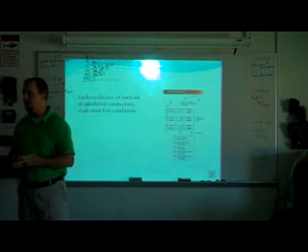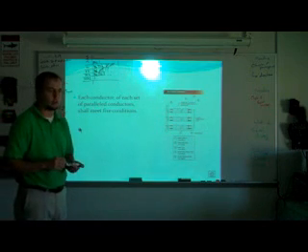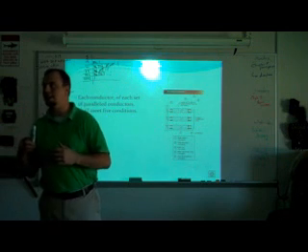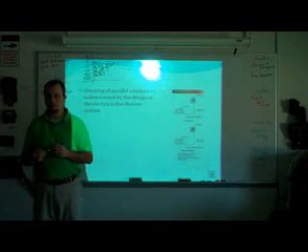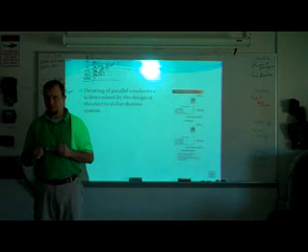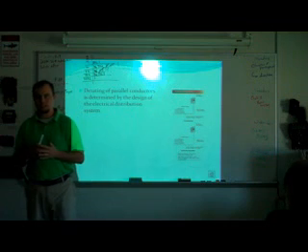Why do they have to be mirror images? Why do you think, Pat? Not so much voltage. One doesn't get more current. Okay, you want them to be exactly the same so that they share the current exactly the same. So let's split that current in half, right? One will get half of the current. Don't say volts, just say current. It has to be the same length, size, material, insulation and connection.